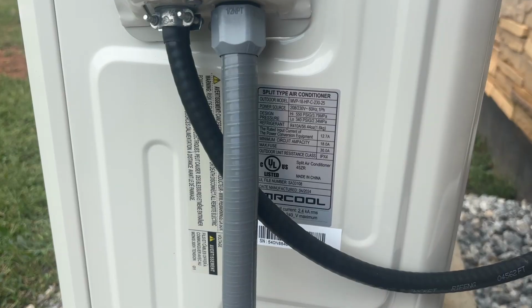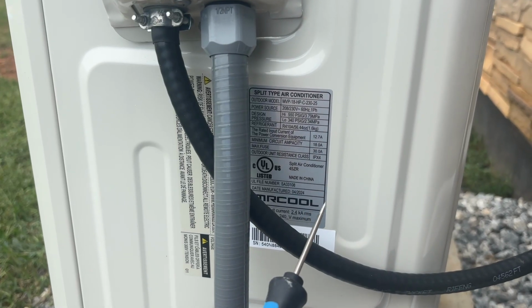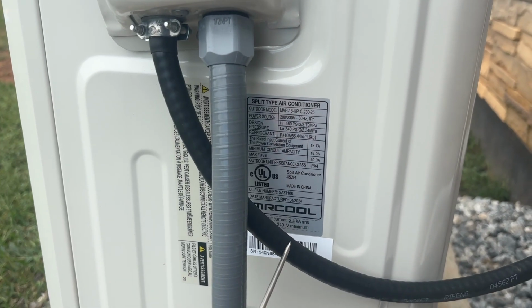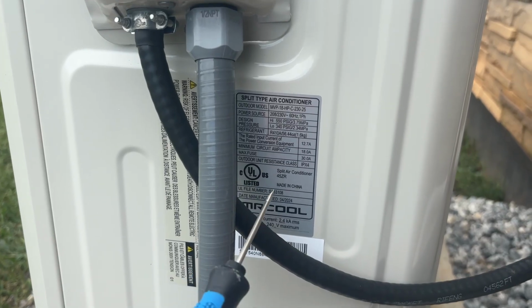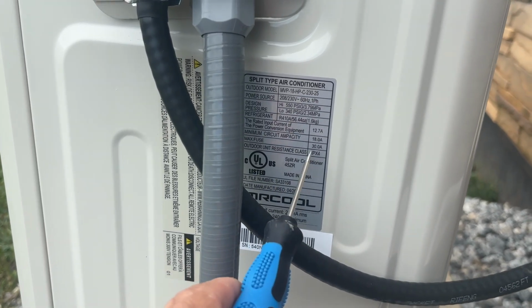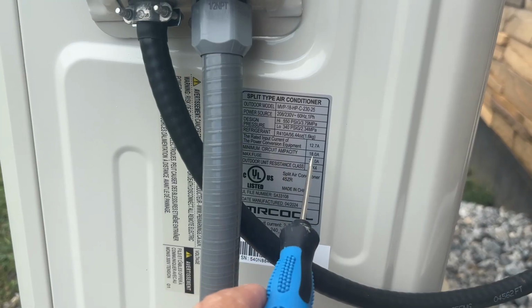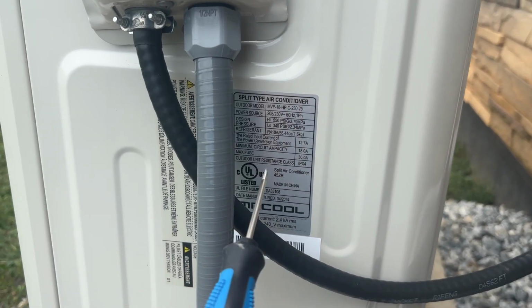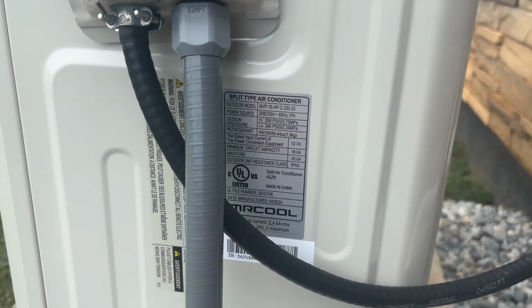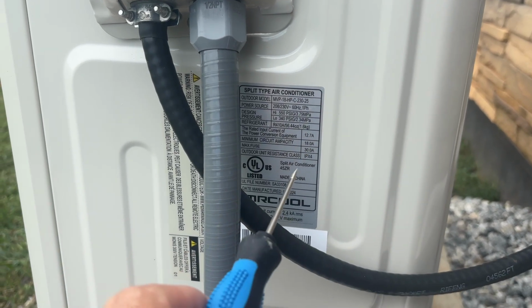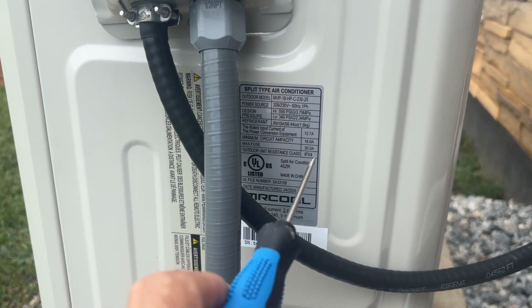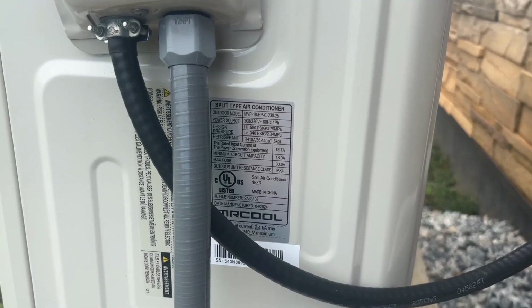I have a 30 amp breaker on this unit, and by the NEC, if I have a 30 amp circuit, I'm going to use number 10 cabling. So I have a 10-2 wire, and we'll show you that here in a minute. Minimum circuit ampacity is 18 amps. So this thing can pull 18 amps at a time. And with 10-2 cable, we meet that requirement as well.